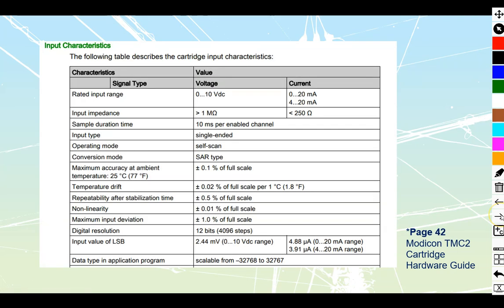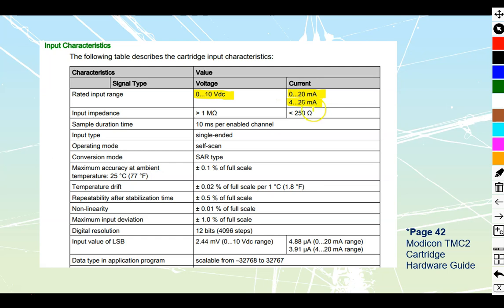The cartridge can take in both voltage at 0 to 10 volts DC or current at 0 to 20 milliamps or 4 to 20 milliamps if you're looking for that minimum monitoring current.